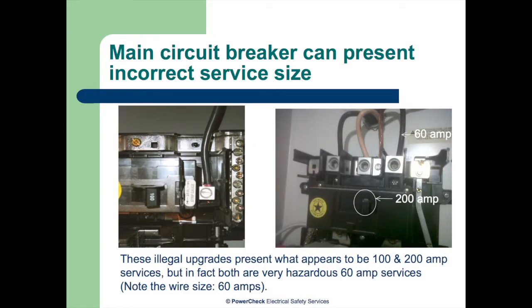Even looking at the service switch itself, 50% is the pull switches, the other 50% is a main circuit breaker. People will often see that main circuit breaker and say, oh, I've got 100 amp, I've got 200 amp. But actually all they've done was change the circuit breaker or the panel itself, with the original 60 amp wires coming into the house. What they did have in this house was no longer a safe 60 amp service. Now they've got a dangerous 60 amp service. So you really need to have an electrical inspector, a master electrician, make comments on service size.